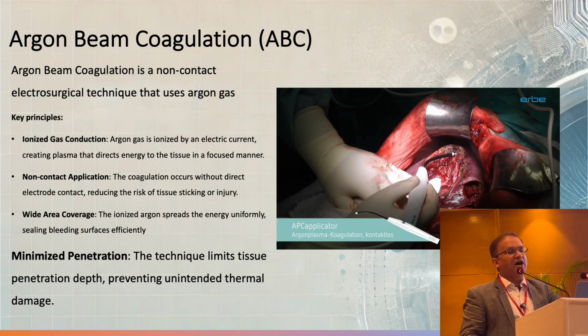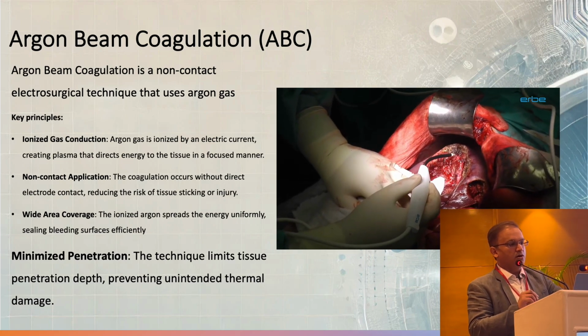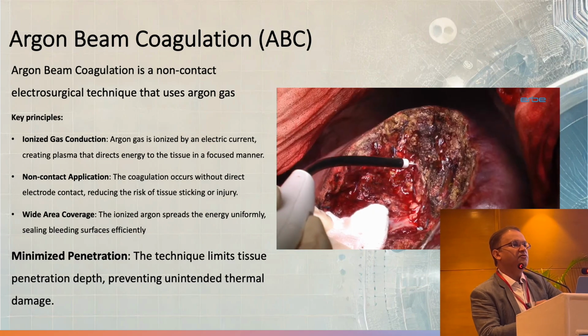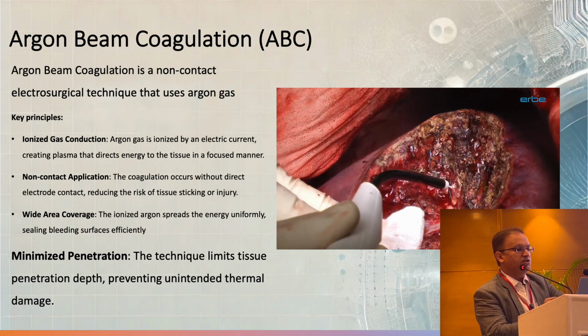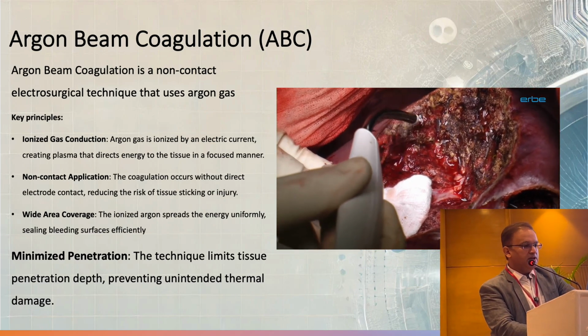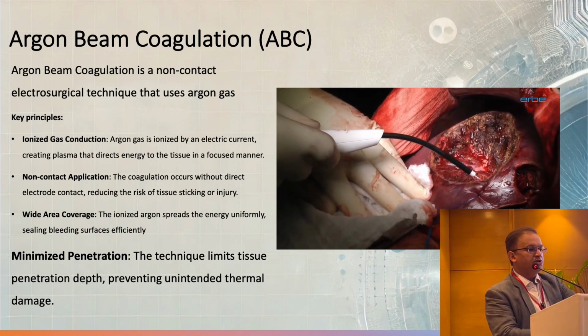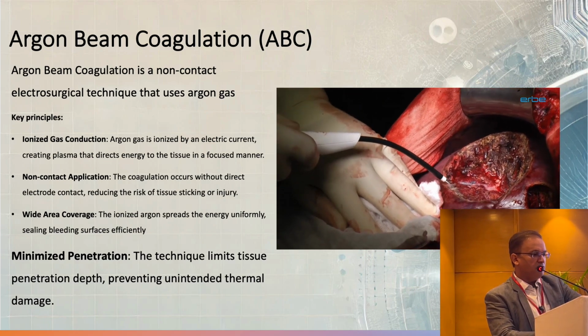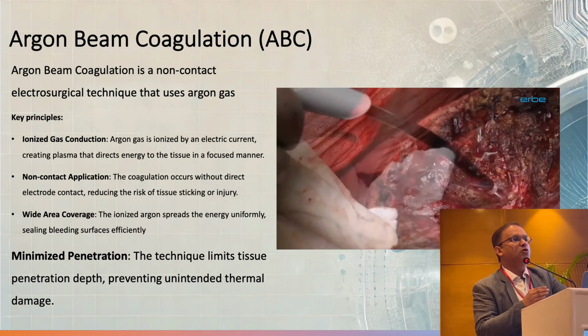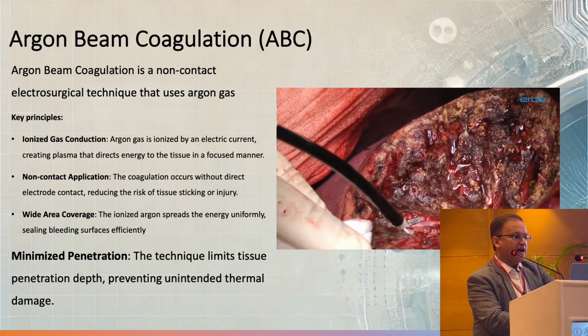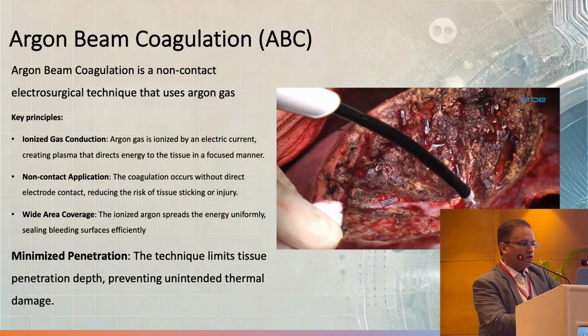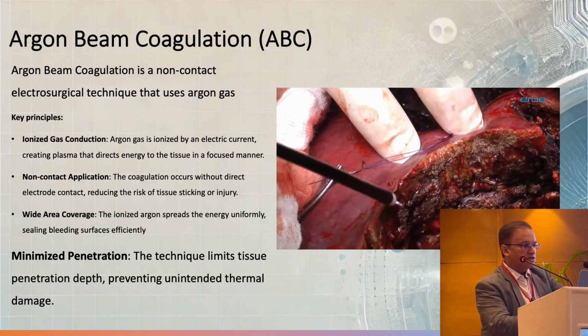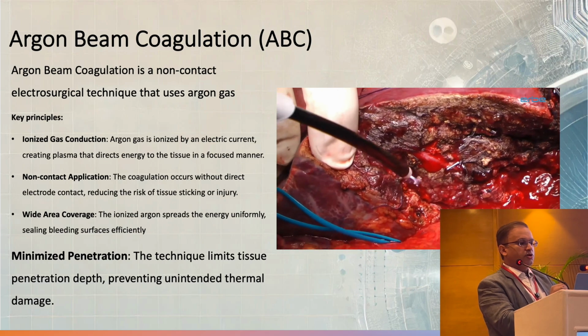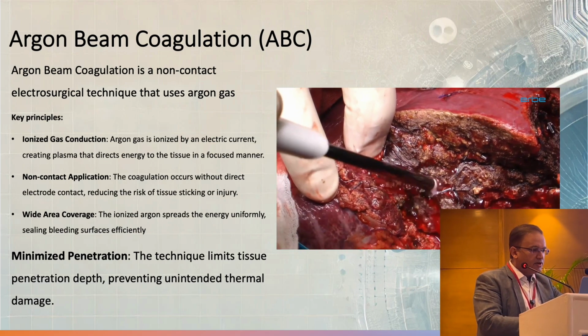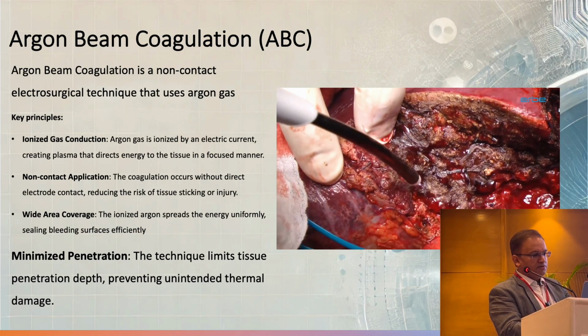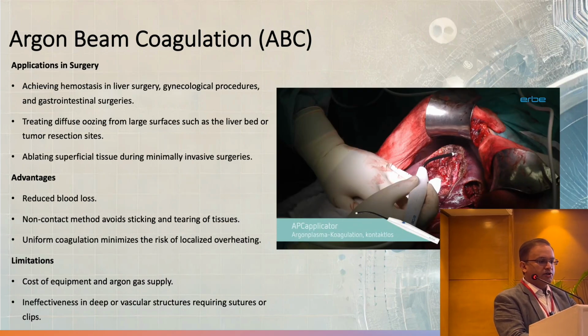The next very fascinating one is argon beam coagulation. These are plasma based coagulation, and these are non-contact. This is the only thing which is basically a non-contact electrosurgical technique that we use. On the right side you can see it is being used on hepatectomy, charring the superficial tissue and causing surface hemostasis. Why surface? Because they have a limitation that they cannot go into depth. So what happens is there is an ionized gas conduction, argon gas, which is released from the probe, and electric current creates a plasma that directs energy to the tissue in a focused manner. The coagulation occurs without direct contact of the electrode, reducing the risk of tissue sticking or injury.